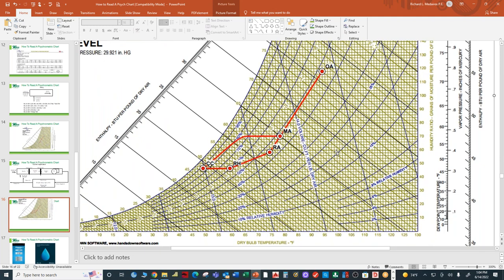So typically when we calculate, I hope I'm answering a question. I'm not necessarily answering the question that was asked, but hopefully we can fumble through this a little bit. When you do the room calculation for sensible and latent, that comes out of your cooling load calculation. When you come up with those two values, if you're using software, the software will give you, for a particular room, the sensible heat value and the latent heat value. If you add those two together, they're the total. So the software gives you the latent, the sensible, and the total.